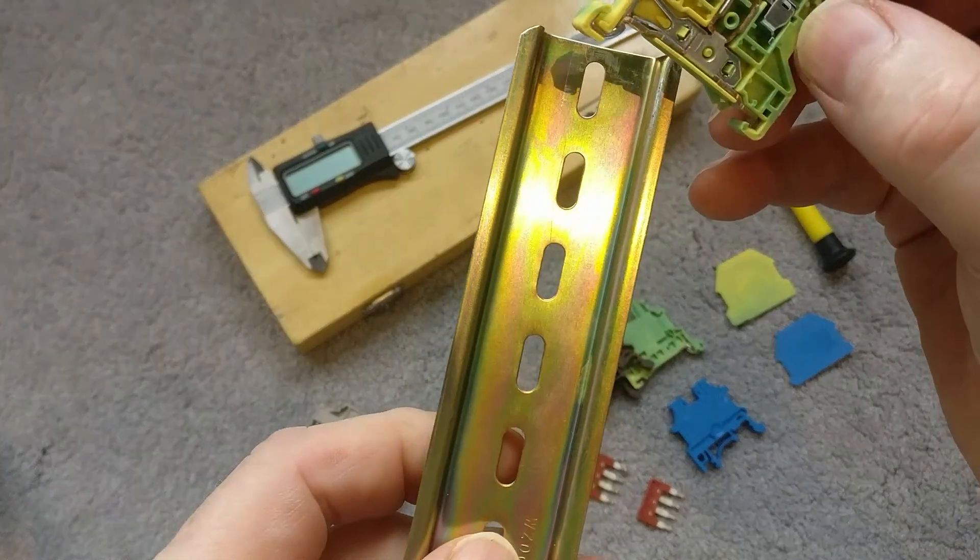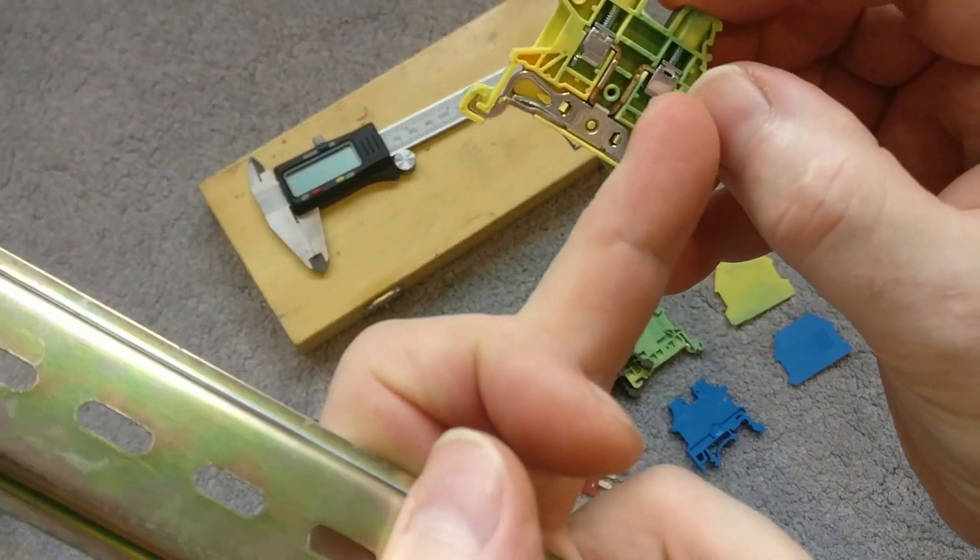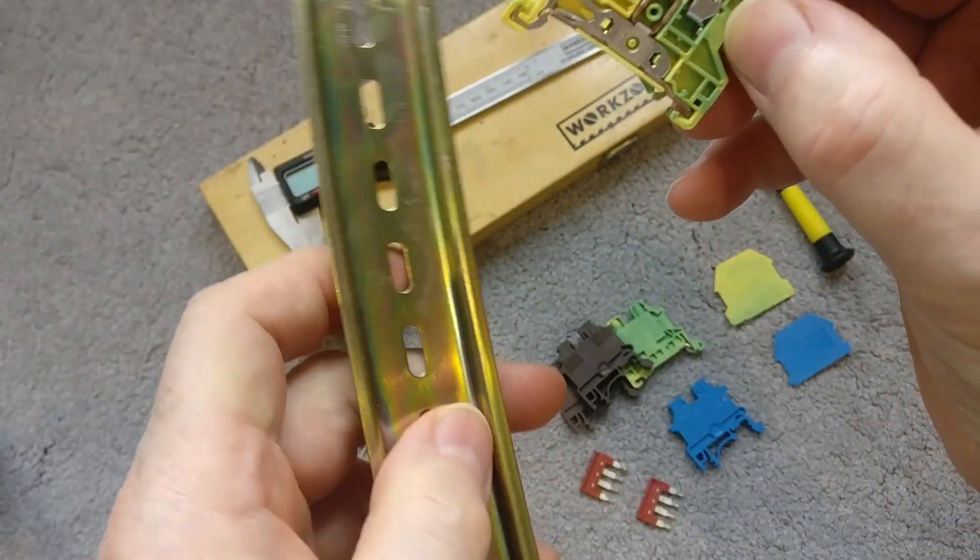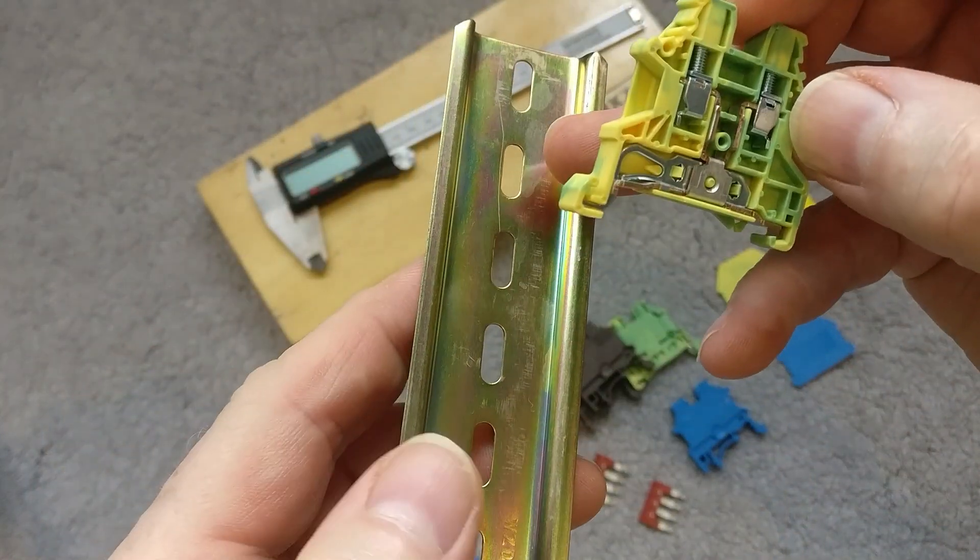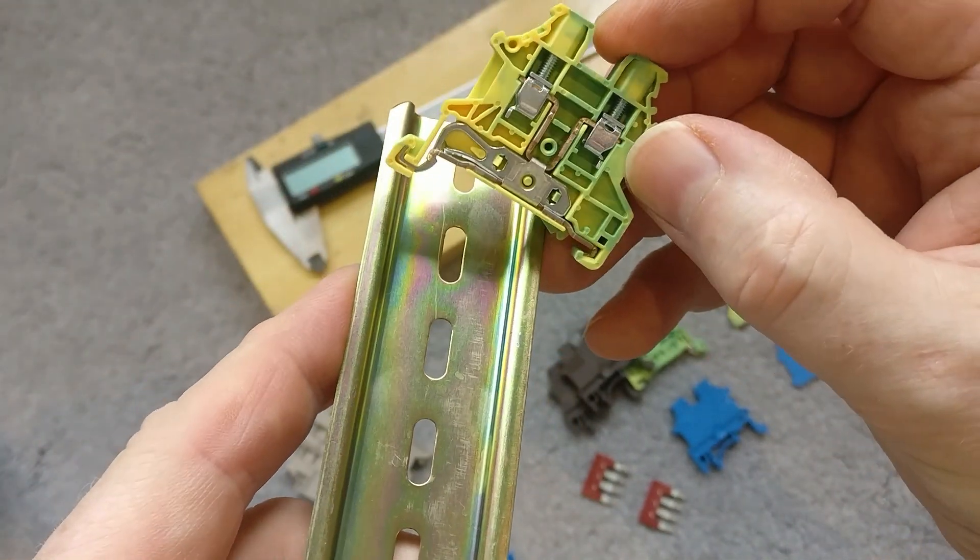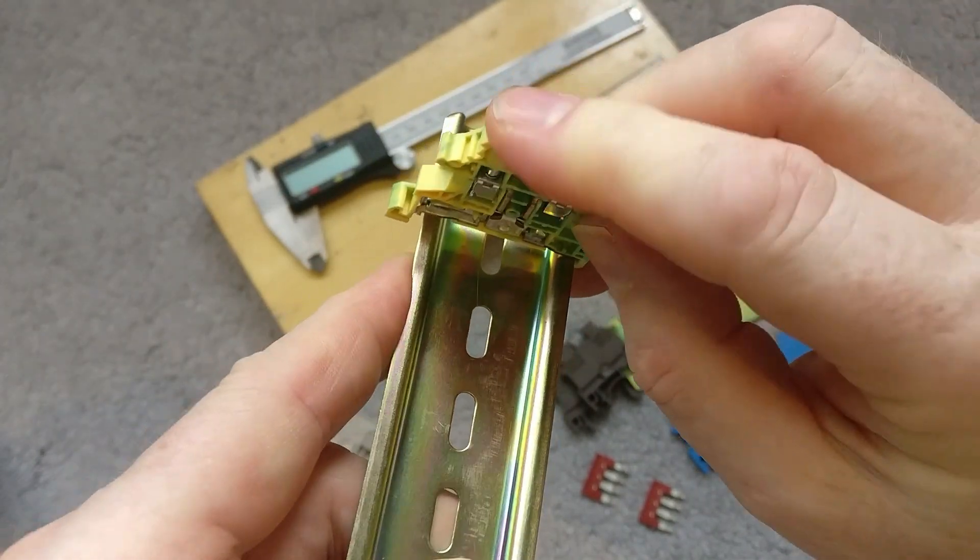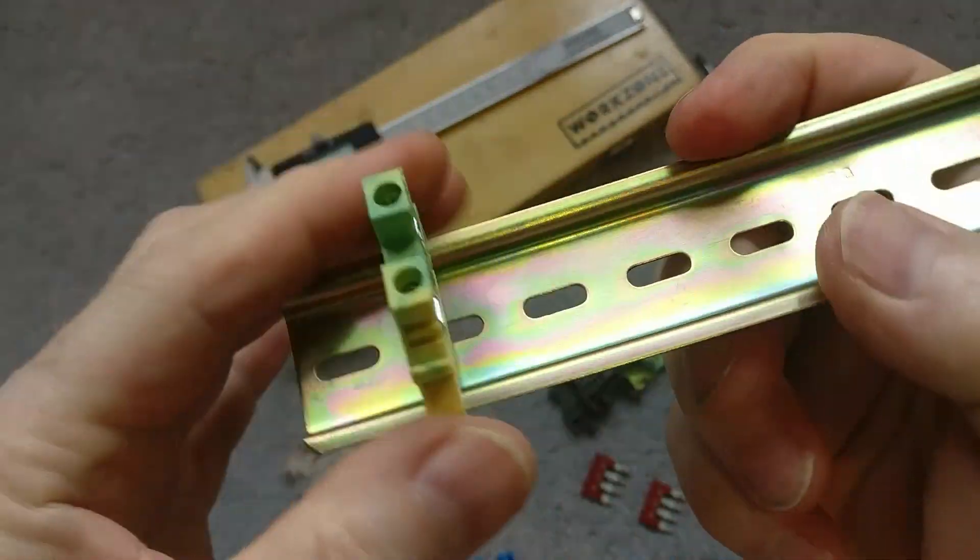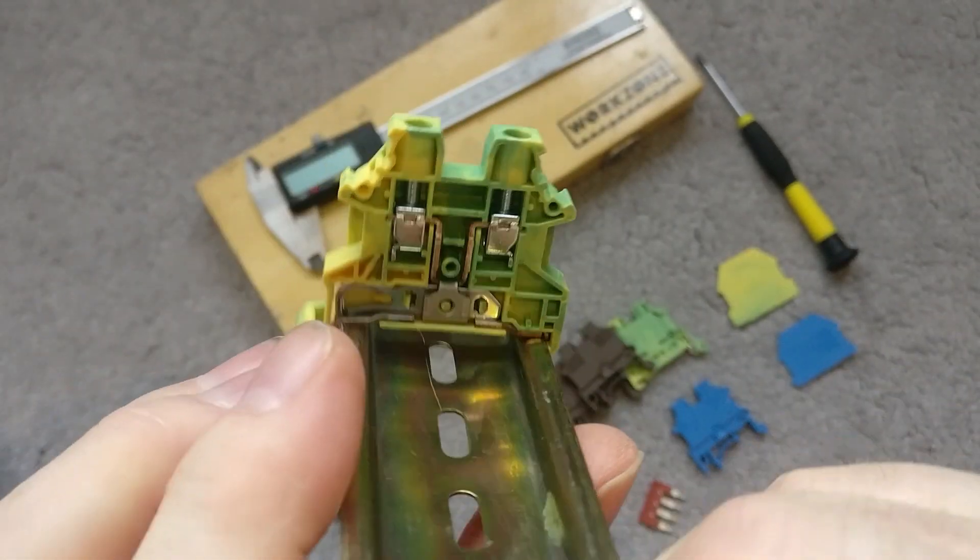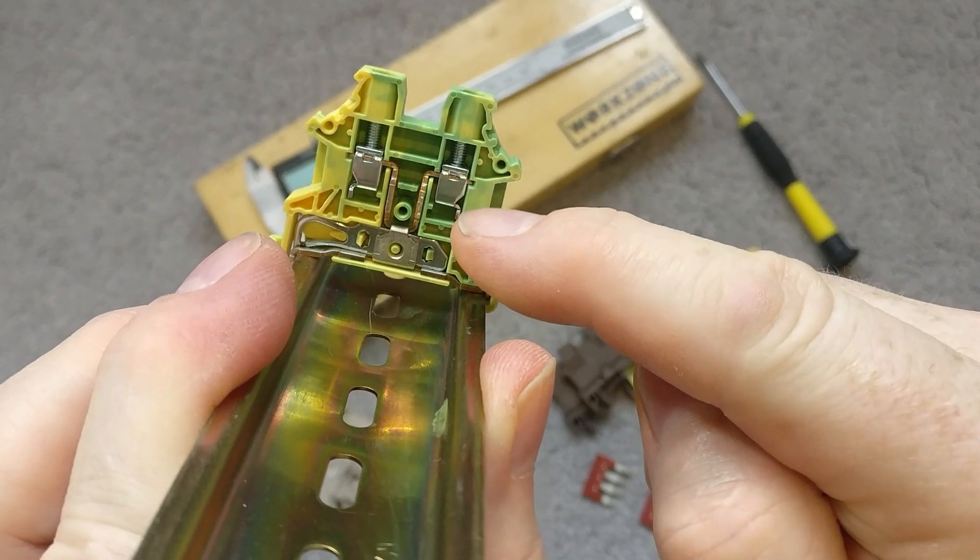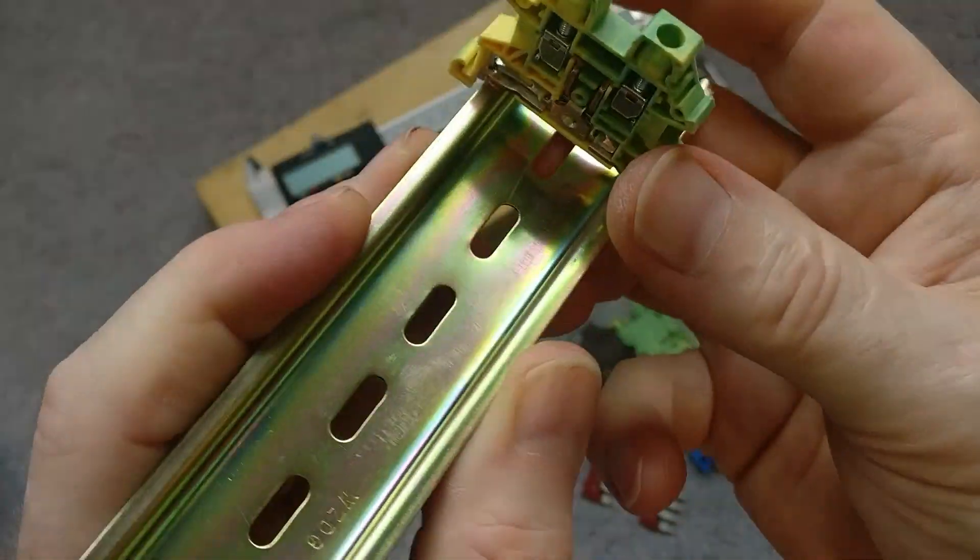These not only provide a flow through for the earth, they also make the DIN rail an earth bar itself. Clip on very similarly, just put it in the back here and then push. That's connected nice and firm, and then you can see the earth will flow through onto the DIN rail, providing you with an earth bar.